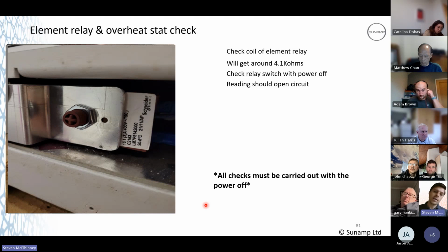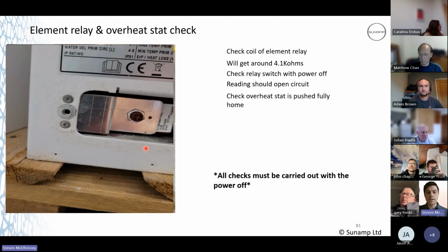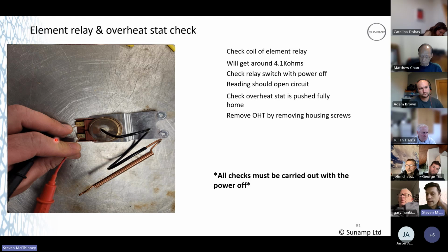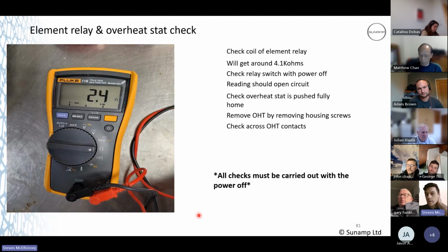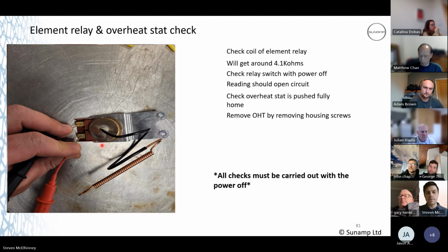Your mechanical overheat stat, so you can see there, that's the limit. So it's going to overheat at 96, and you'll be able to push that button back in when it reaches 90. So it's just a mechanical reset. You can remove it, just remove the 2 screws there in the housing and check across the contacts, and you should be getting continuity. That's just the resistance of my leads here, but you'll get continuity across there. If it's pushed fully home and you're getting open circuit, you know there's a problem with the overheat stat. But generally, the problem I've seen with these is the gas within the phial is released over time, and then the thing just constantly trips.